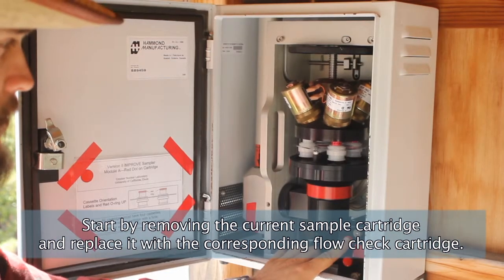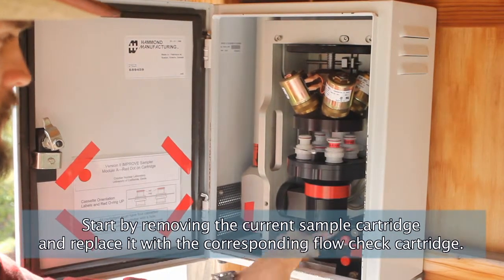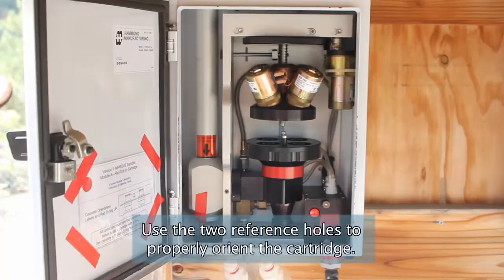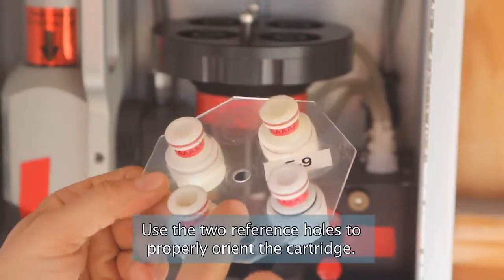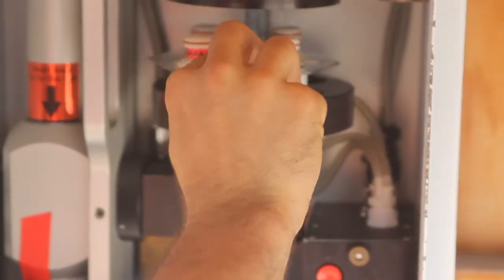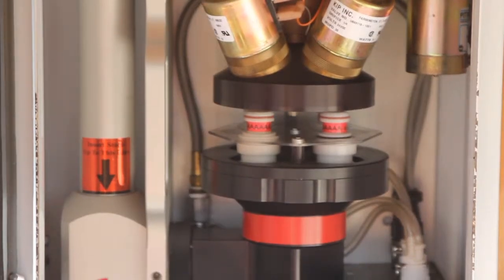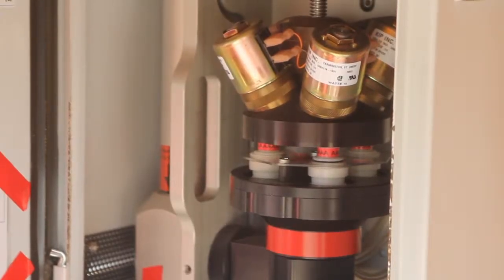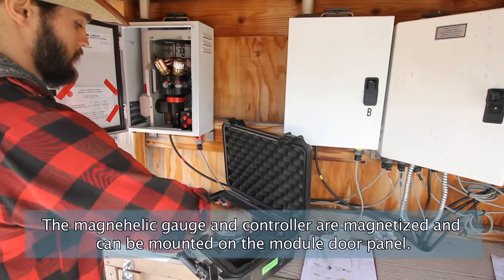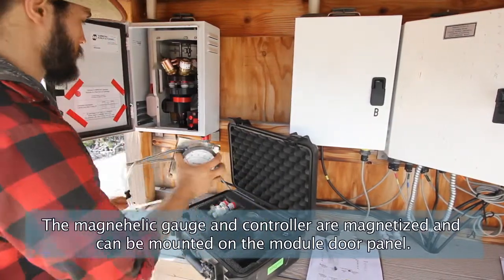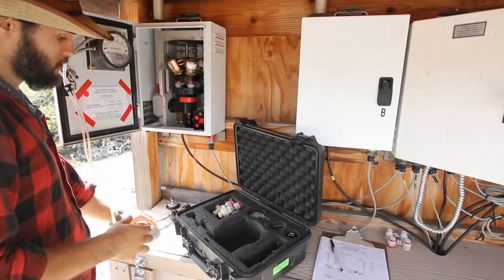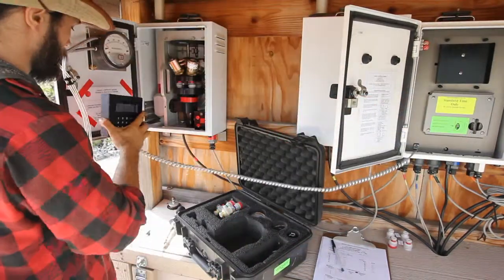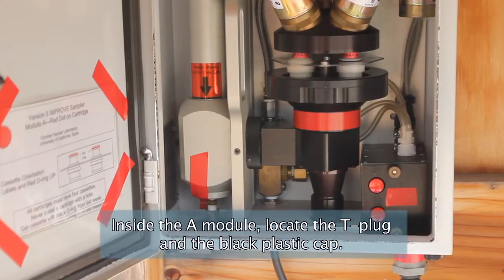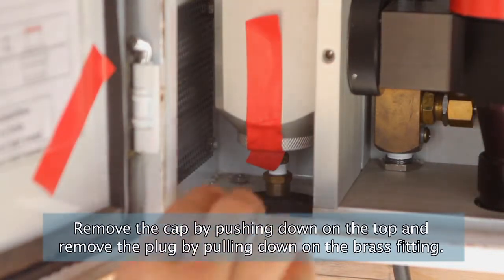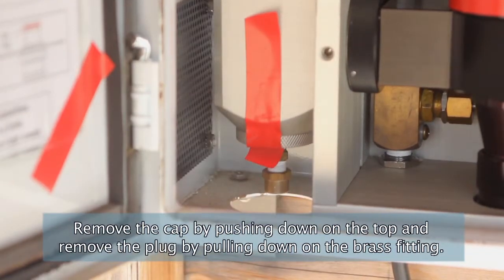Start by removing the current sample cartridge and replace it with the corresponding flow check cartridge. Use the two reference holes to properly orient the cartridge. The Magnehelic gauge and controller are magnetized and can be mounted on the module door panel. Inside the A module, locate the T-plug and the black plastic cap. Remove the cap by pushing down on the top and remove the plug by pulling down on the brass fitting.